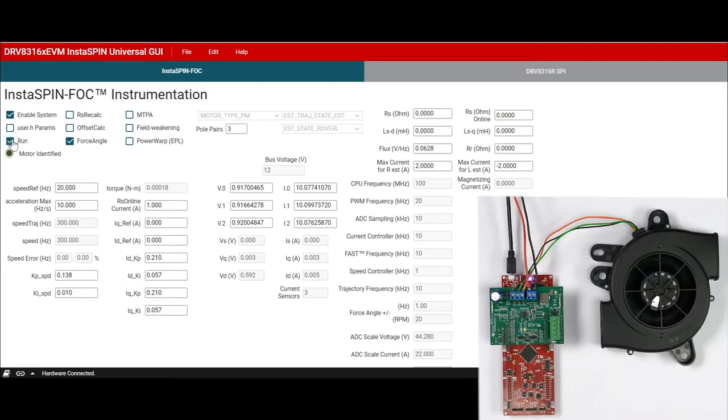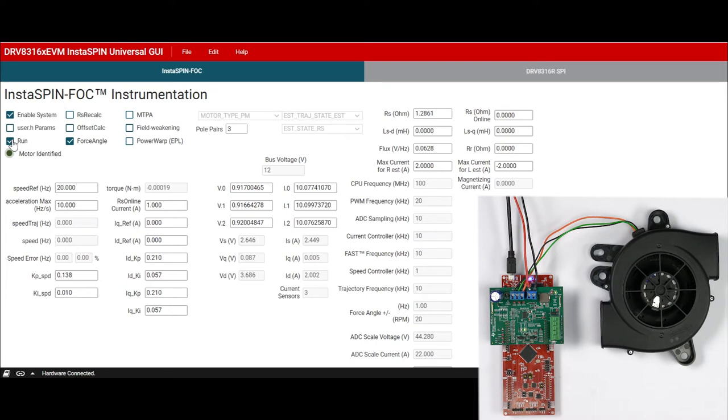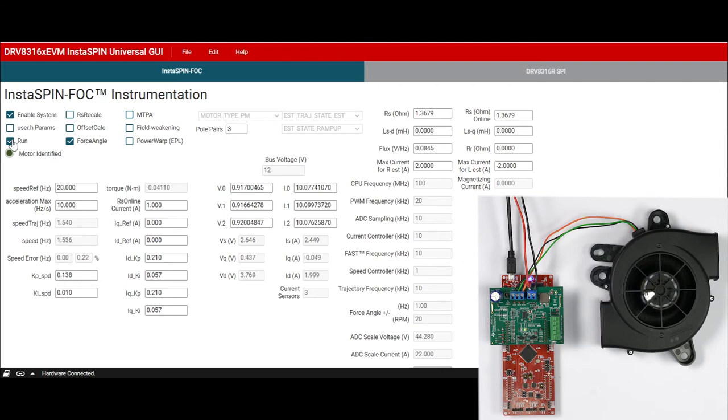For the next couple of minutes, the algorithm will automatically identify motor parameters such as online motor phase resistance, direct and quadrature inductance, and motor flux. This motor identification algorithm is great for identifying and saving motor parameters in firmware without any measurement tools needed.